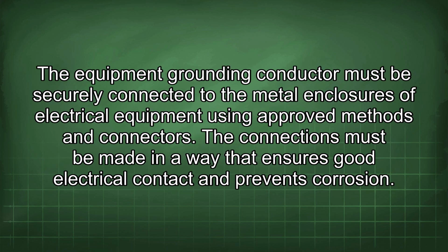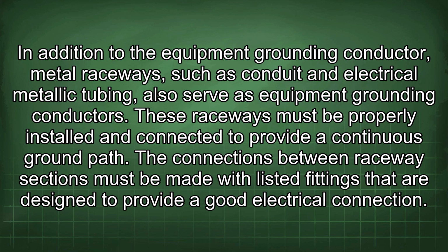The equipment grounding conductor must be securely connected to the metal enclosures of electrical equipment using approved methods and connectors. The connections must be made in a way that ensures good electrical contact and prevents corrosion. In addition to the equipment grounding conductor, metal raceways, such as conduit and electrical metallic tubing, also serve as equipment grounding conductors. These raceways must be properly installed and connected to provide a continuous ground path. The connections between raceway sections must be made with listed fittings that are designed to provide a good electrical connection.